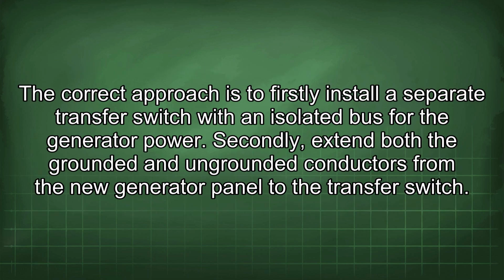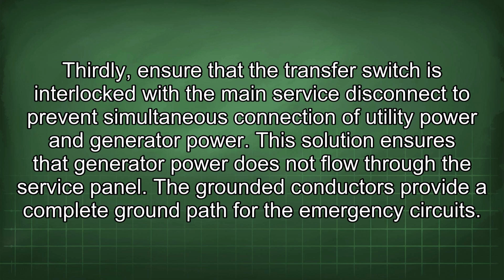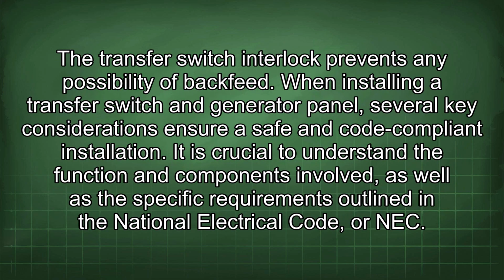The correct approach is to, firstly, install a separate transfer switch with an isolated bus for the generator power. Secondly, extend both the grounded and ungrounded conductors from the new generator panel to the transfer switch. Thirdly, ensure that the transfer switch is interlocked with the main service disconnect to prevent simultaneous connection of utility power and generator power. This solution ensures that generator power does not flow through the service panel. The grounded conductors provide a complete ground path for the emergency circuits. The transfer switch interlock prevents any possibility of backfeed.